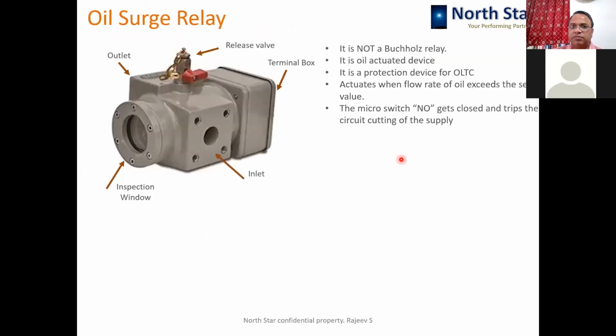Oil surge relay, it is not a Buchholz relay, it is actually an oil actuated device. It is a surge actuated device, and it is provided in the OLTC. So Buchholz and OSR are not interchangeable. They have their own function, they have their own way of working. Since the OLTC is subjected to oil surges, especially when the OLTC is operating and huge arcing is happening inside, there is a disturbance created in the oil because of the force of the arc, and because of that force, the oil gets disturbed and a surge occurs inside the OLTC, and that oil surge rises towards the conservator, and when this OSR is in the circuit, the OSR gets operated because of the surge. So it is not gas operated, okay, it is surge operated.